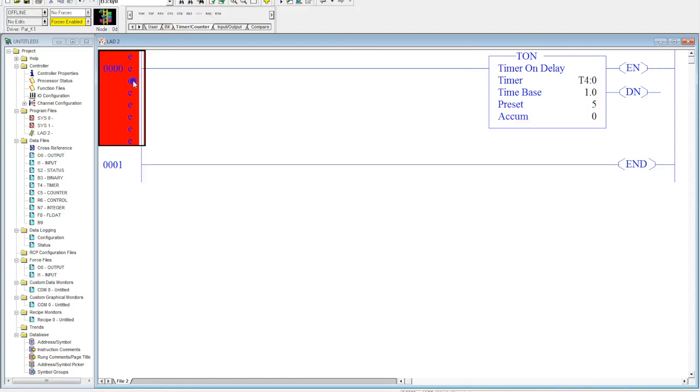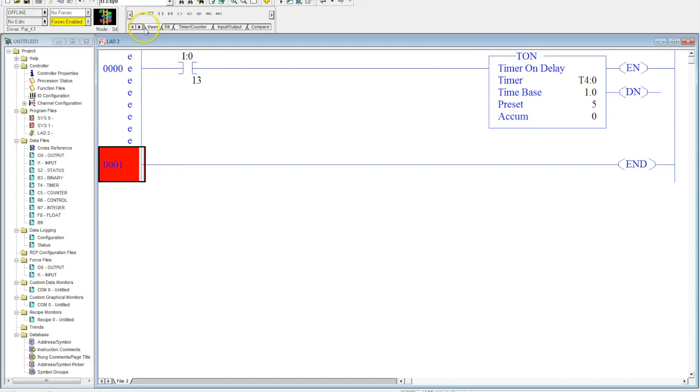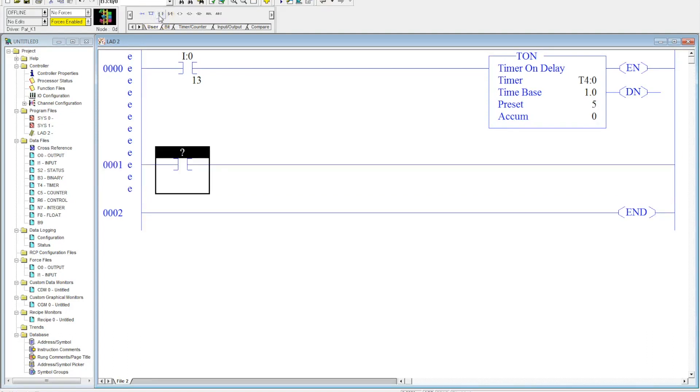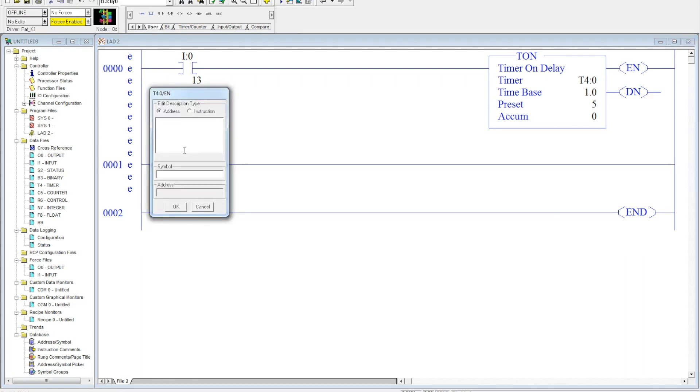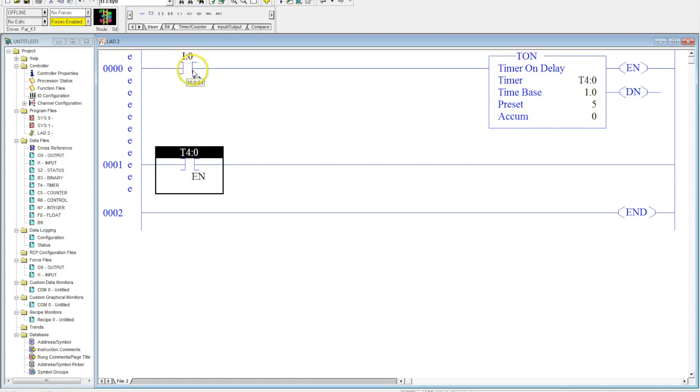Here, I'm just going to show you how it works. I'm going to put a simple input in here that will activate the timer. Now these timers have three different contacts associated with them. The first one is the enable bit, and this is how it's addressed: T4:0/EN. This enable bit will turn on whenever your timer is powered.